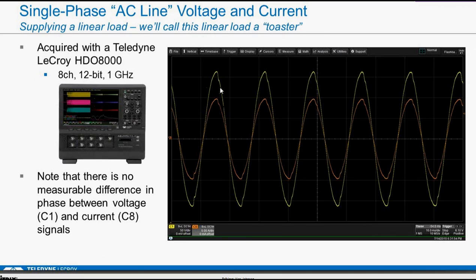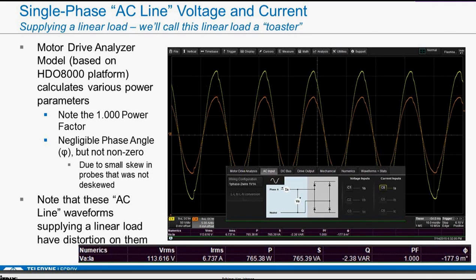And you can see, though, there is some distortion here. So even what we think of as pure sinusoids are really never pure sinusoids. I did, just for yucks, take our motor drive analyzer, which measures three-phase and single-phase power, and I calculated all the quantities. You can see the voltage here is 114 volts RMS, a little less than rating, and the current's about 7 amps RMS. And we calculate the power. There is a very small amount of reactive power, so small it's kind of lost in the rounding. You get a very near zero phase angle, and that rounds up to a 1.0 power factor. So this is kind of what we would expect.